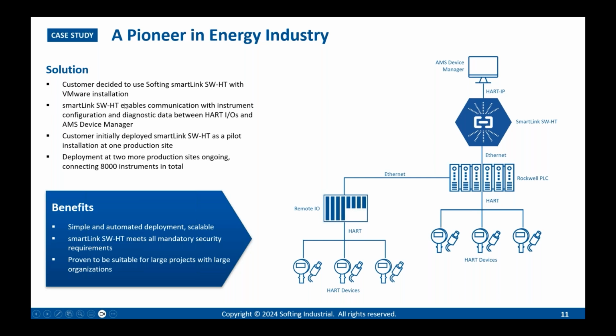The HART devices, as you can see here, were connected to the remote IOs and also directly to the PLC. From the remote IO to PLC, the communication is Ethernet, and also from PLC to the SmartLink software version the communication is Ethernet, and via HART IP they were able to have all the data. So the configuration and diagnostic data was easily available.